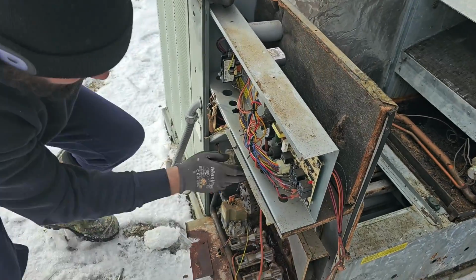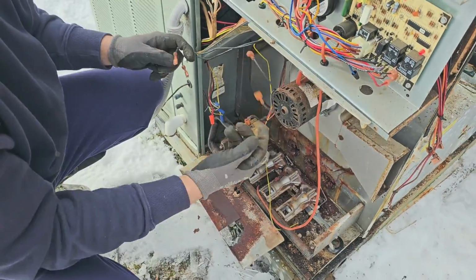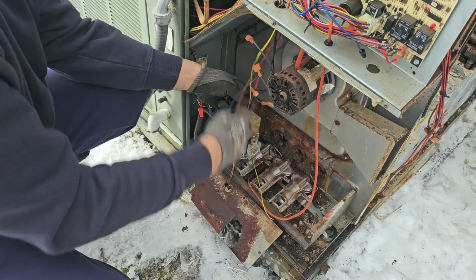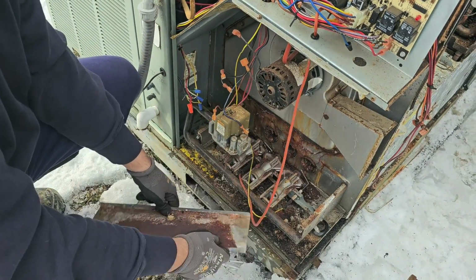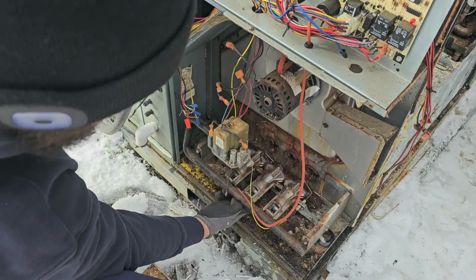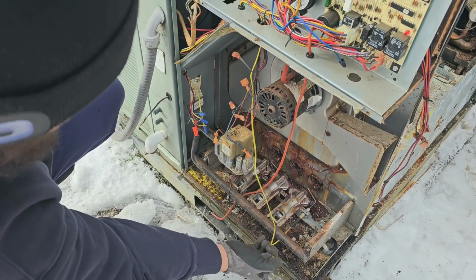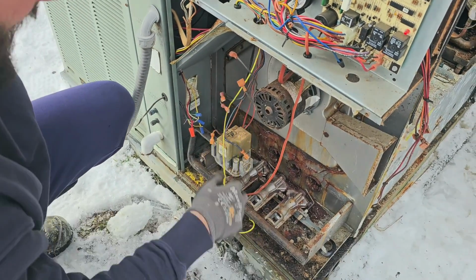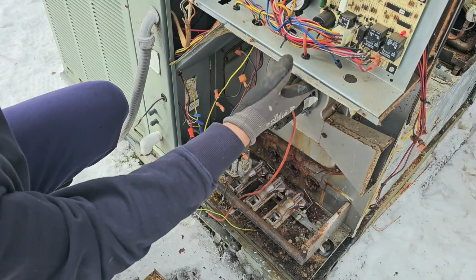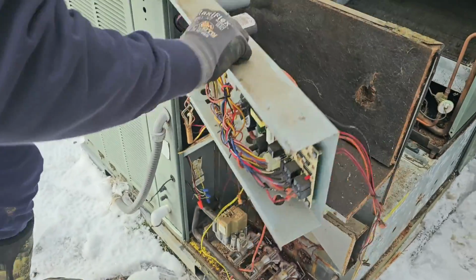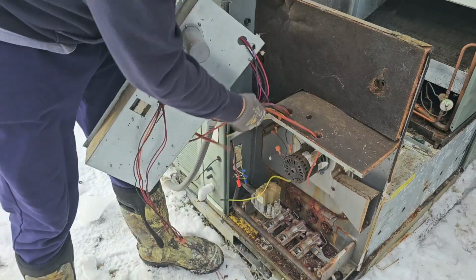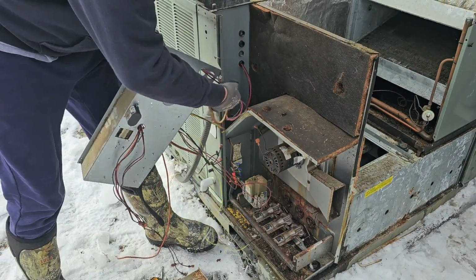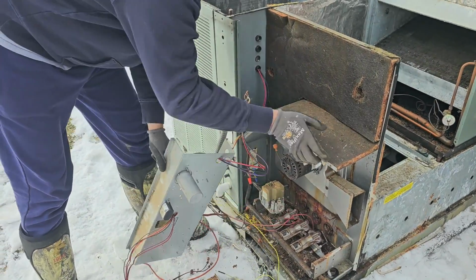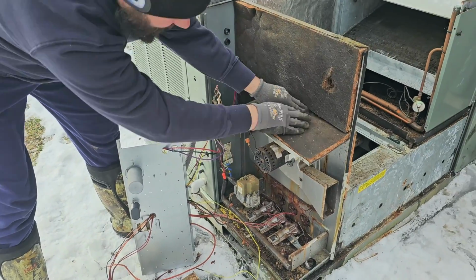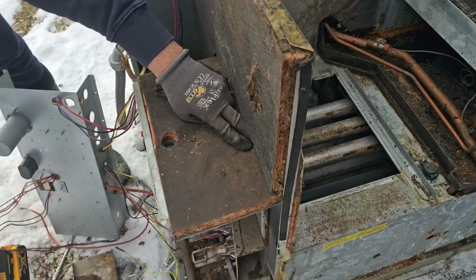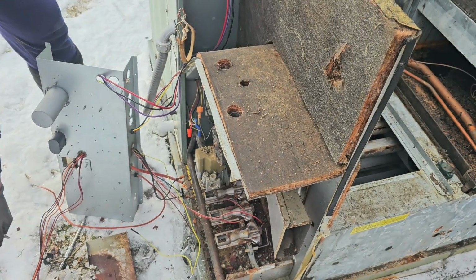Now all these wires for the inducer motor, the gas valve, the rollout switch, the igniter, the flame sensor, and the pressure switch tube, all these have to be removed. See? Pull all those through. And then the last thing, we got to take the screws loose from this panel, and that's the reason I've got my extension.